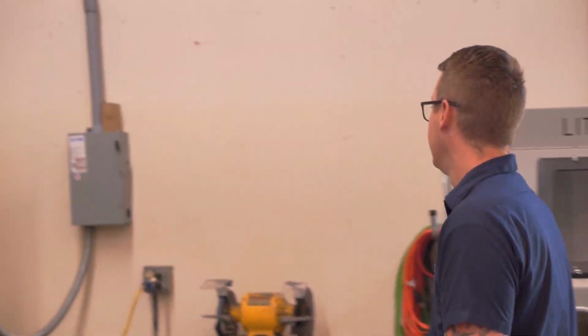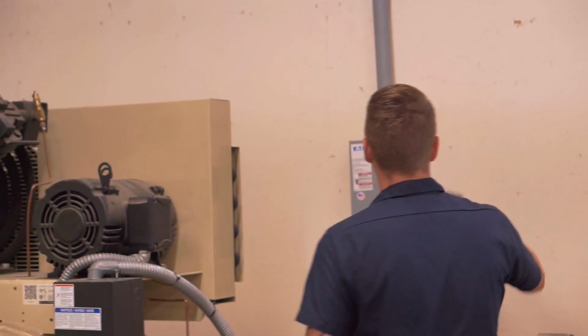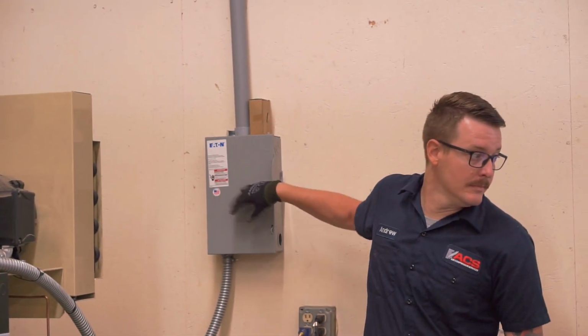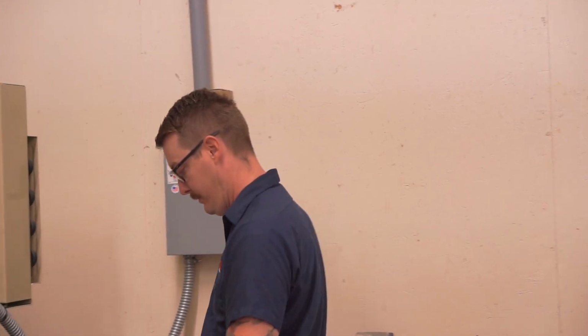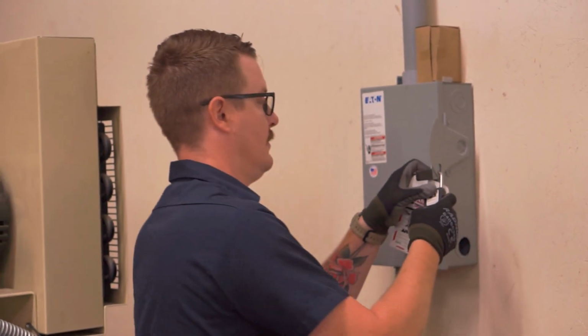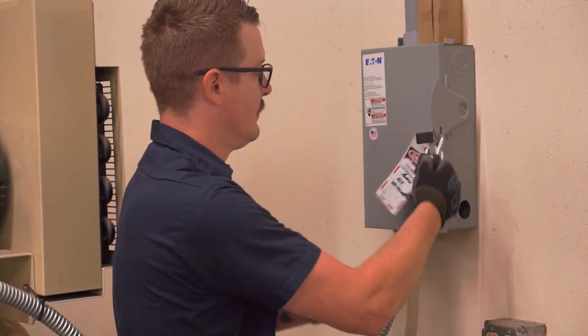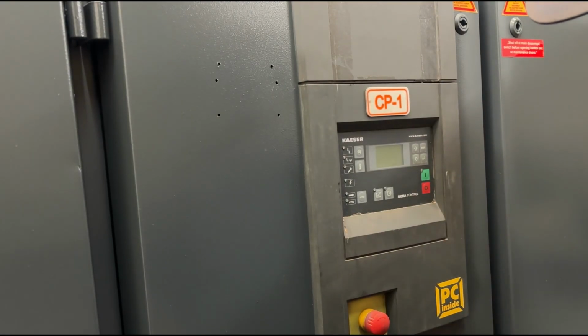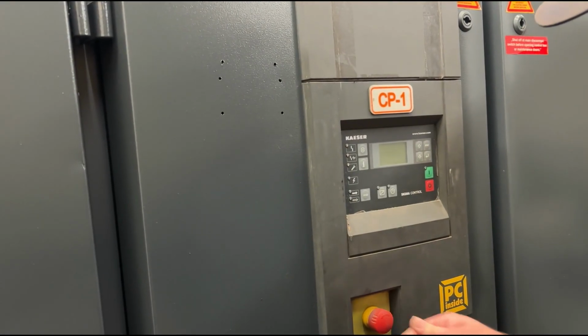Lockout-tagout is the first and most important part of safety protocol. Notice our technician during the process. As he locks out the handle, he uses his right hand and turns away to the left. This is to avoid a possible arc flash. He then checks to make sure the panel is locked securely. Check the control panel to verify the power is disconnected.